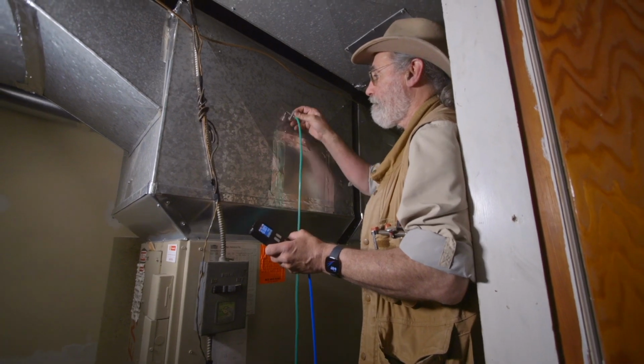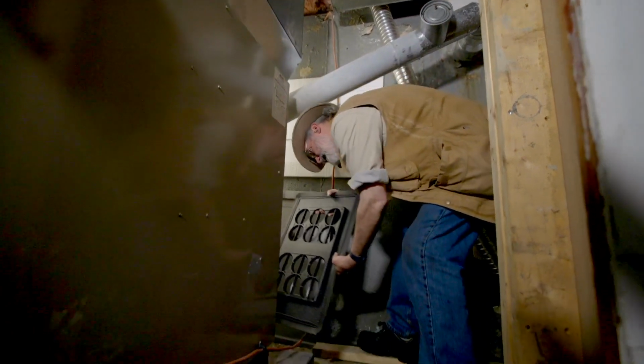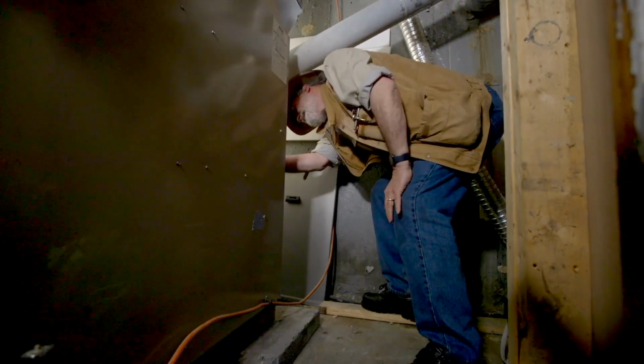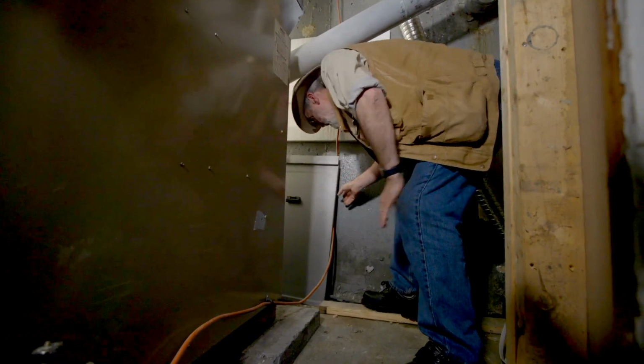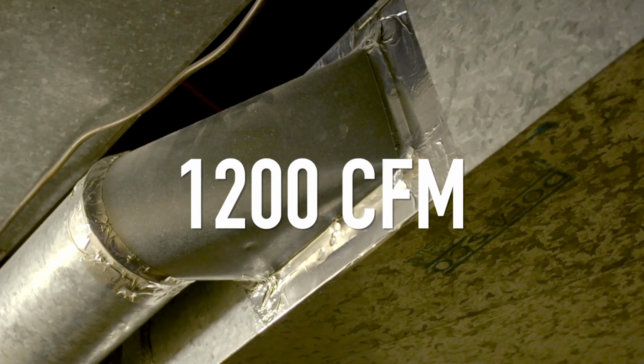You measure the supply pressure pushing out of the furnace, you measure the return pressure, and then you replace the filter on the furnace with an airflow grid. So using the pressure and airflow measurements that we got, it turns out we can move almost 1200 CFM, which is good enough for a 3-ton heat pump, which is the right size for this house.